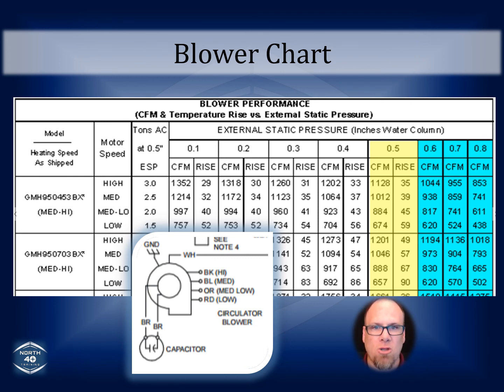But over the long haul, here's what happens. It doesn't dehumidify properly. You've now overcharged the system, so it's not running efficiently. You've ruined some of the capacity, some of the efficiency. The compressor is not running, electrically speaking, as efficiently as it should. It's going to draw more amps on startup, so the likelihood of it tripping a breaker or blinking the lights is much higher than if you'd just done it the way that you should have done it.